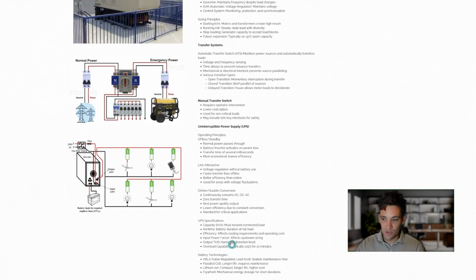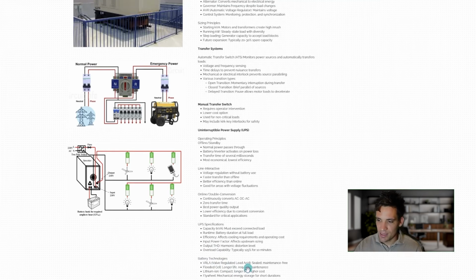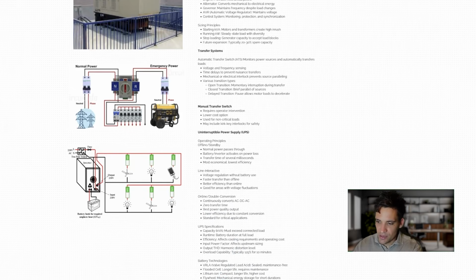When we're talking about UPS systems, we're talking about the capacity, the same as a generator, in kVA. We're talking about the runtime, how long they can run providing full load. So are they a 2-hour UPS? Are they a 4-hour UPS? The efficiency: do they waste power? Input power factor: because UPS are power electronics and involve rectifiers, they'll cause harmonics on your system because they're converting the AC to DC and then DC to AC, because batteries produce electricity at DC. And the overload capacity. And then finally, there are a couple of different battery technologies.